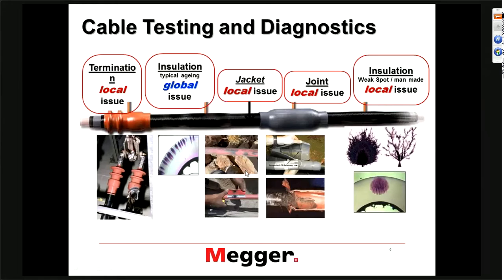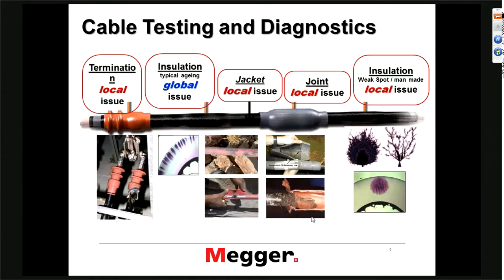If you look on the top picture, you can see there were some pretty bad rocks in that trench, putting pressure on it and eventually causing the failure of the cable. In the joint splice area, most of the splice failures occur at both ends of the splice, where the splice overlaps with the cable. Not so many faults are seen anymore in the middle of the splice. On the right-hand side, you see a cross section of an XLPE cable with very localized insulation damage — one huge water tree.